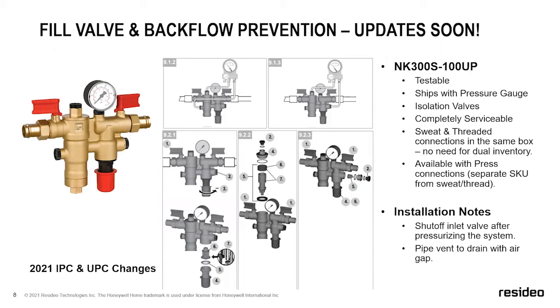So the new IPC and UPC code books, these are approved inside those books. We've had a couple jurisdictions that have fought us a little bit on this type of a product. So the code book may read today that the jurisdiction requires a testable atmospheric vent backflow assembly. Well, that is now approved in the 2021 code books. With that being said, it does take time for jurisdictions to adopt code books. I know a couple areas that are still running on the 2015 code books. So although it will be in the 2021, just something to note, it may be a couple of years before your local jurisdictions actually do end up approving it.